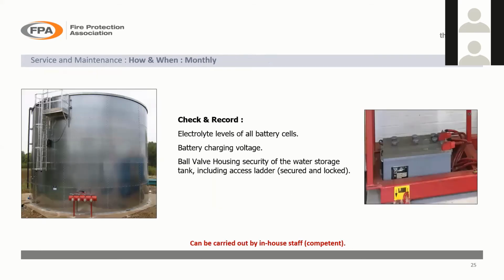The monthly things to look out for really relate to the tank and the batteries. Check the batteries are level and check the water levels and things like that, and check the ball valve security. We come on to this a little later, but just check that your ball valve is secured and locked, and nobody can just get up there and put things into your tank. Again, this can be carried out in-house, and you don't have to get a specialist contractor in for that, as long as you've got people who are trained to do so.